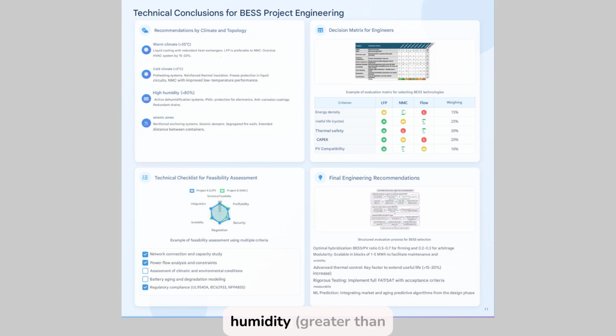For high humidity, greater than 80%: IP65 protection, anti-corrosion coatings, active and passive drainage. For seismic zones: reinforced anchoring, seismic dampers, containers with structural separation and firewalls. These recommendations are not optional. They are design requirements if the desired lifespan and availability are to be met.